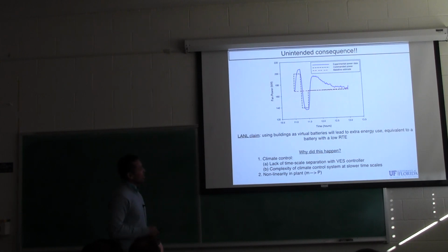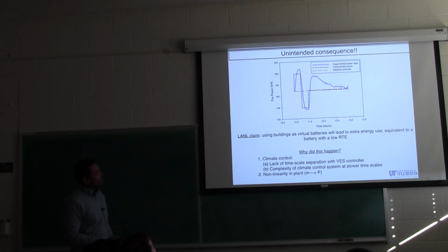And they designed a controller. The controller is very simple. It basically says, okay, if I want to increase power consumption by this much, I'm going to reduce the temperature set points by these many degrees. That's the mapping they came up with.